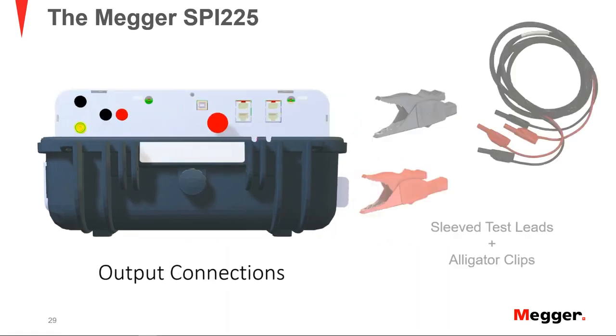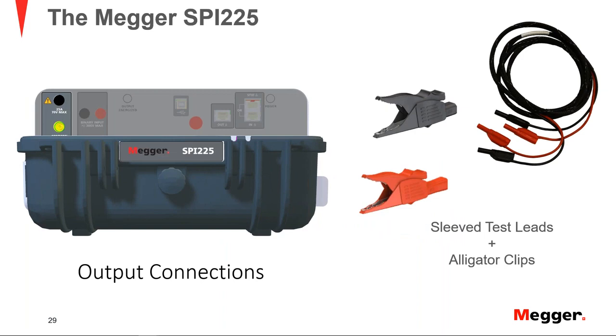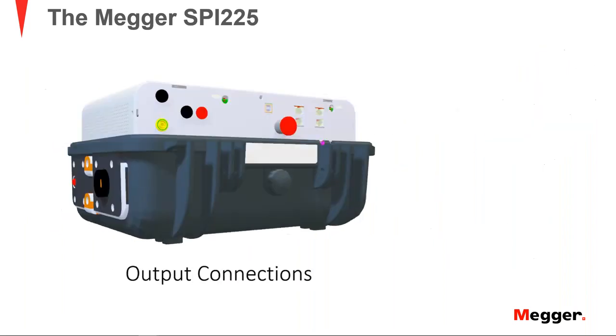Typically, if you're using this tab, you can use the sleeve test leads, which we include with the unit, with alligator clips. And these test connections are excellent for terminal screws and pins where the spade lugs cannot be used, for small breakers and obviously when not using higher currents. Next, if we look at the side of the instrument, we have the two remaining tabs. As you can see, we have a common connection, which is displayed in the bottom. So we will use this common for either the 125 amps tab or the 500 amps tab displayed in the upper part.